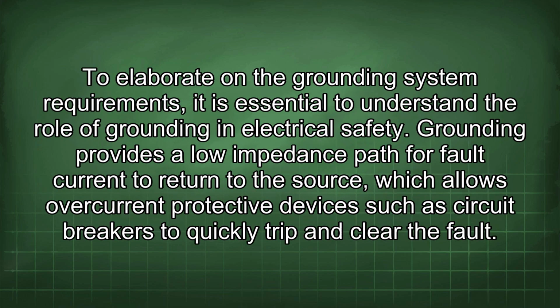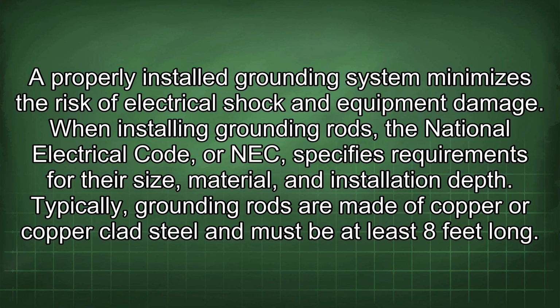To elaborate on the grounding system requirements, it is essential to understand the role of grounding in electrical safety. Grounding provides a low impedance path for fault current to return to the source, which allows overcurrent protective devices such as circuit breakers to quickly trip and clear the fault. A properly installed grounding system minimizes the risk of electrical shock and equipment damage.